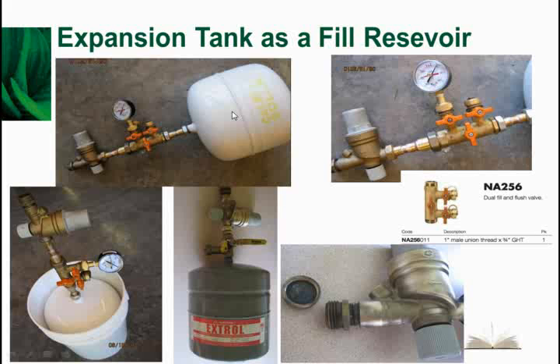So it's a handy little way to just take a little bit of fluid to a job to refill a system, or to leave it on a job until you're sure all the air is out of the system. This little tank here actually fits inside a 5-gallon bucket, so if there's any drips or any mess, it just drips right in the bucket. I've made a couple different versions of this. There's a small one with probably a number 15 Amtrol expansion tank on that.